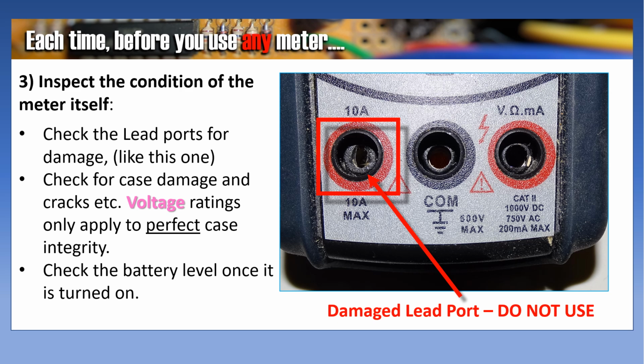So let's take a look at this particular picture. Check the lead ports for damage like this one. You can't put the lead in properly. You can see it is deformed. Check the case for damage, cracks, etc. Voltage ratings only apply to perfect case integrity. Then check the battery level once it's turned on.